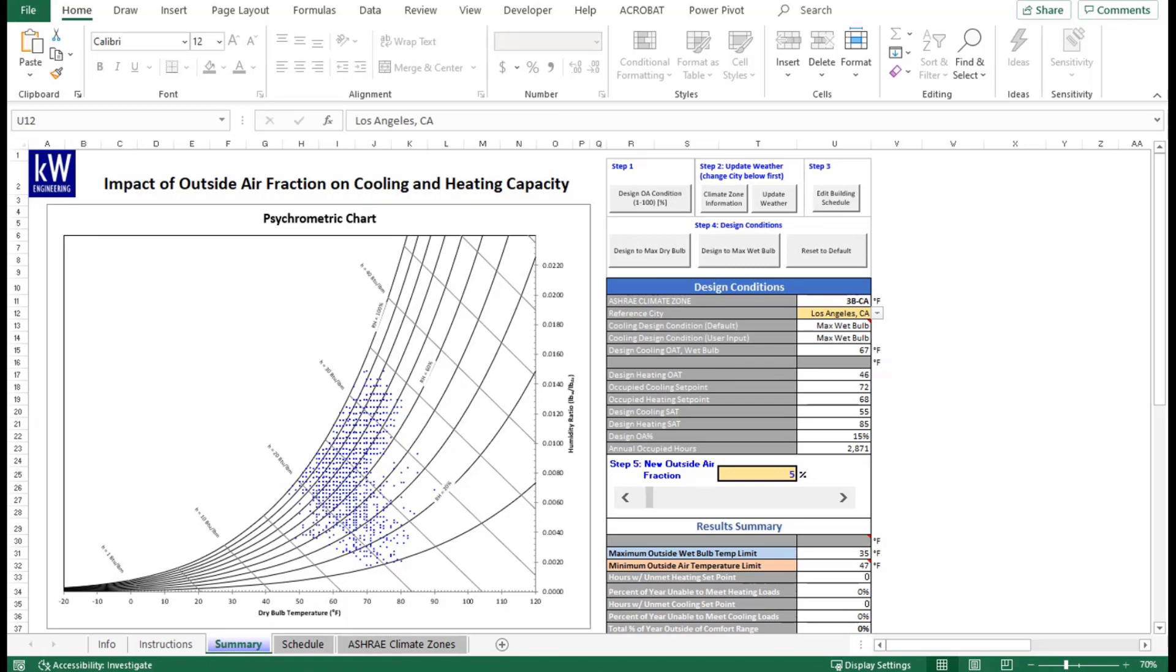To get started, the first thing we're going to want to do is go to Step 1 in the tool under the Summary tab and click on that macro here which says Design OA Condition 1 to 100%. That will give you a pop-up message which tells you the typical value of a building, which is typically 15% to 30%. You can find this information in your mechanical equipment, test and balance reports, or your building automation system.